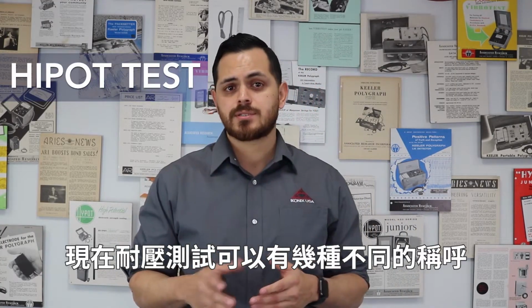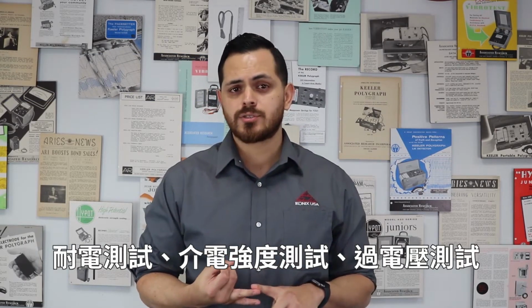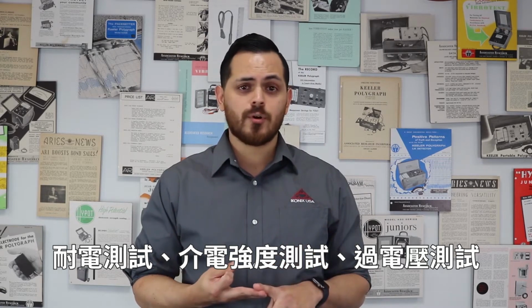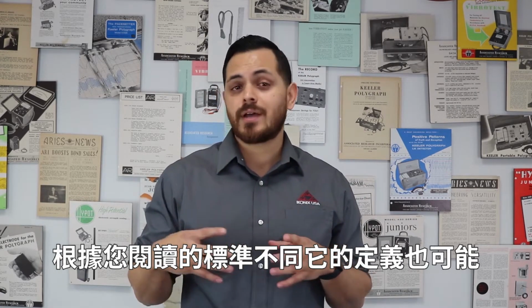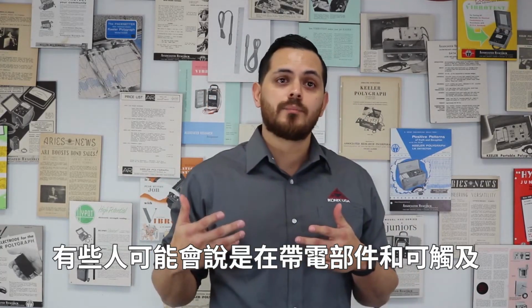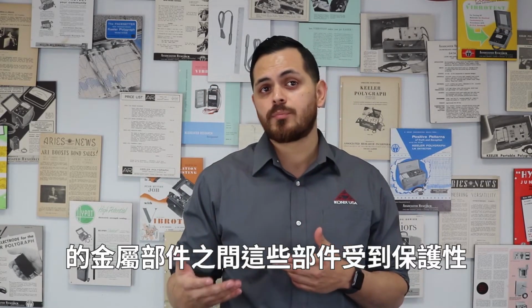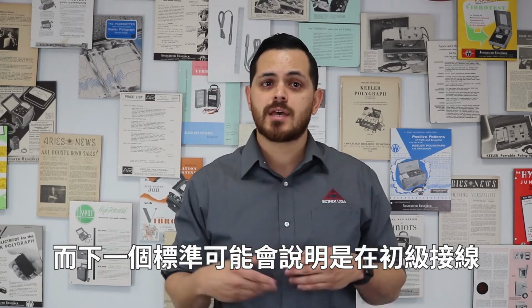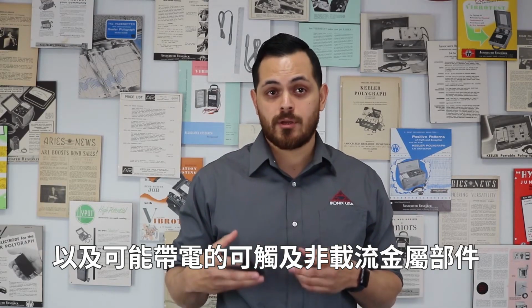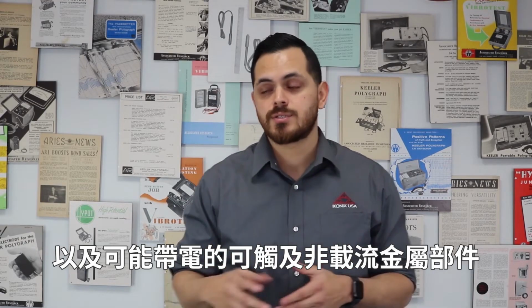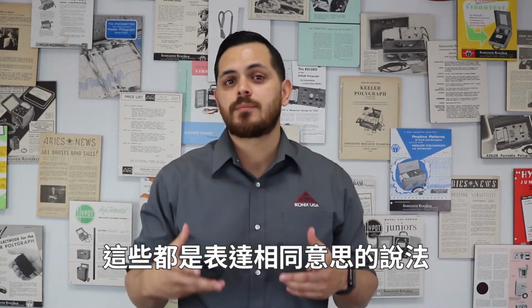Now the Hipot test can be called a few different things: dielectric withstand test, dielectric strength test, over voltage test. It can also be defined differently depending on what standard you're reading. Some might say between live parts and accessible metal parts, which are protectively earthed, while the next standard might state a test between primary wiring and accessible non-current carrying metal parts that can become energized. These are all ways of saying the same thing.